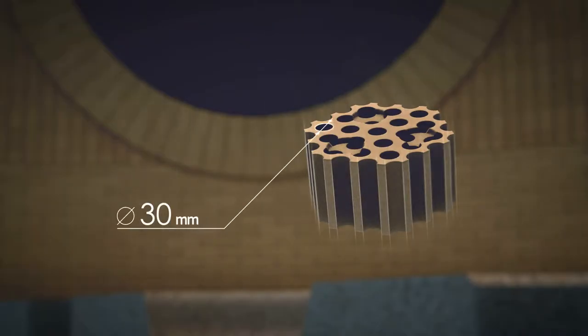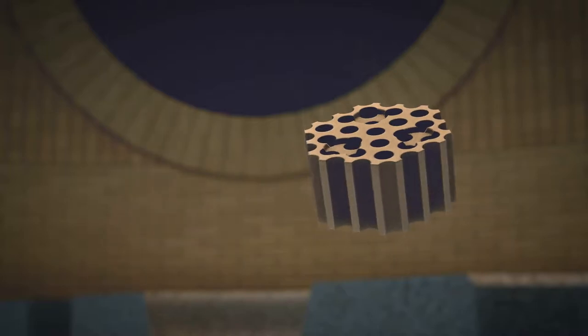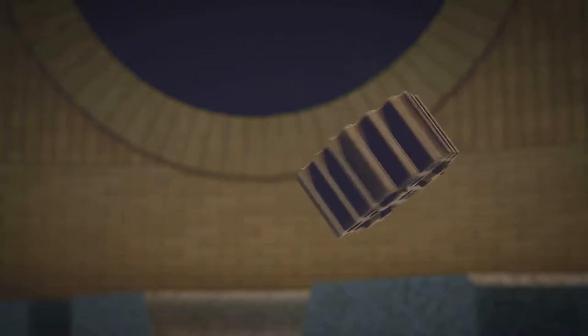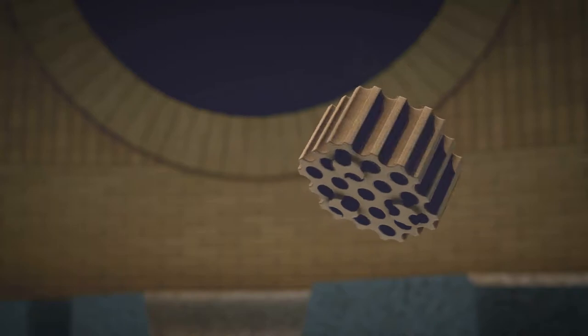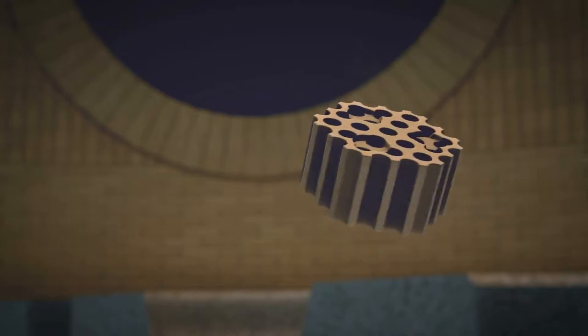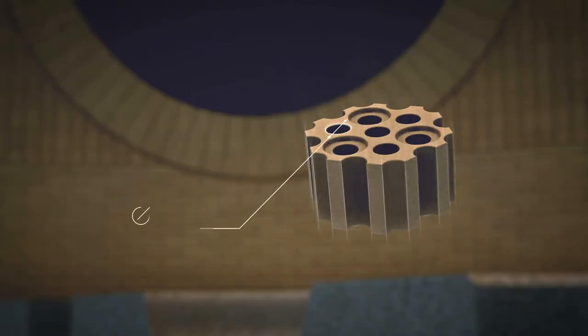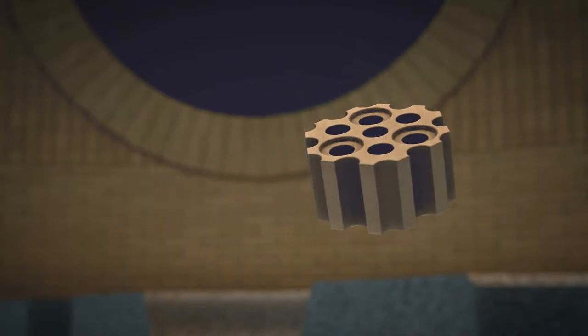Distribution of zones made of different refractory bricks over the checkerwork height is calculated in such a way that there are no conditions for hole clogging with dust and slag. Therefore, over the entire period of operation, the checkerwork with holes of any diameter remains clean.